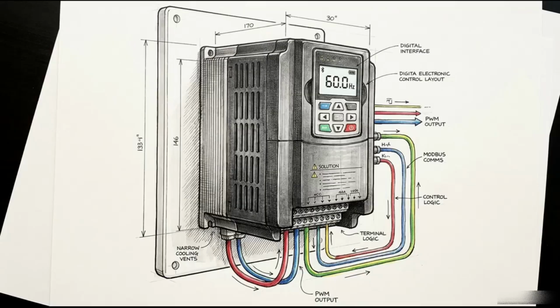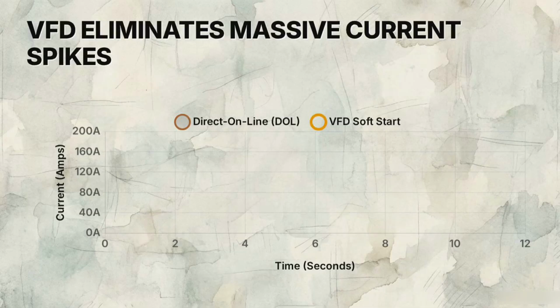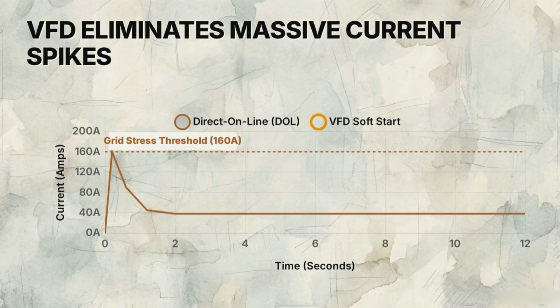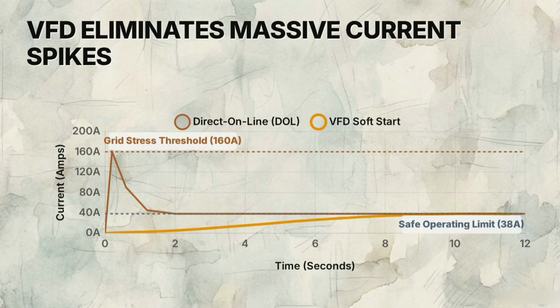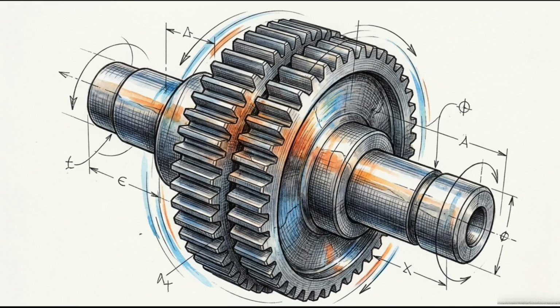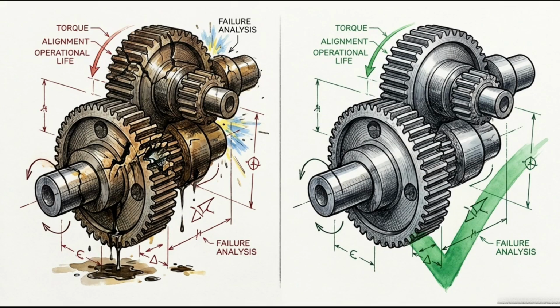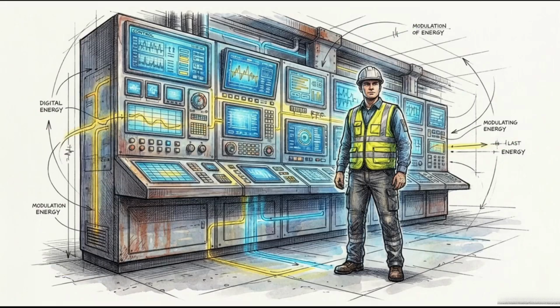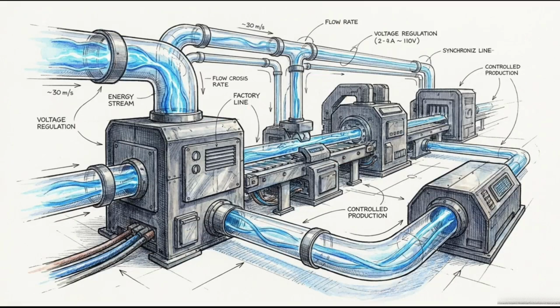Preventing this violent inrush surge requires moving away from simple mechanical switches and instead adopting dynamic, precise electronic control. The variable frequency drive, or VFD, allows an engineer to bypass the zero back EMF problem entirely. A standard start creates a 160 amp spike, placing immense stress on the grid. The VFD implements a soft start. By slowly ramping up frequency, it builds back EMF artificially. The motor reaches full speed while current never exceeds safe limits. This controlled ramp also provides a critical mechanical benefit. It eliminates the violent physical jerk associated with a sudden start. Preventing this instant torque spike reduces the wear on gearboxes and coupling shafts, significantly extending the operational life of the equipment. Industrial engineering is the precise modulation of energy, transforming the raw, volatile physics of the utility grid into a controlled, predictable tool for production.